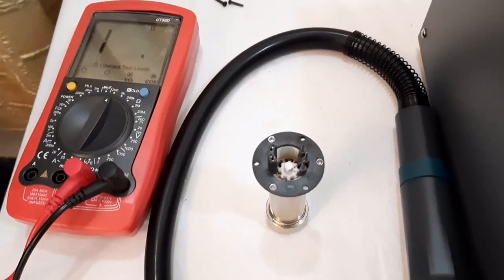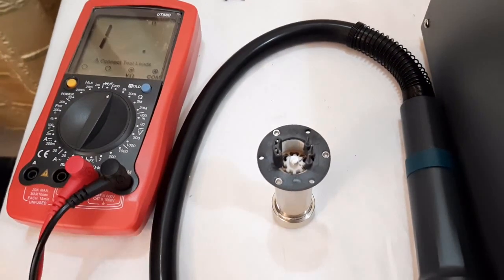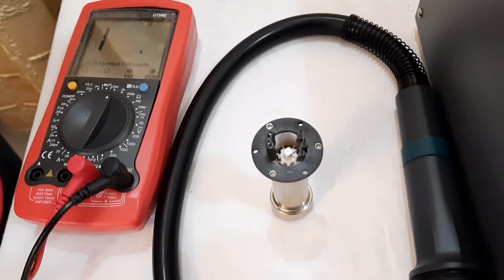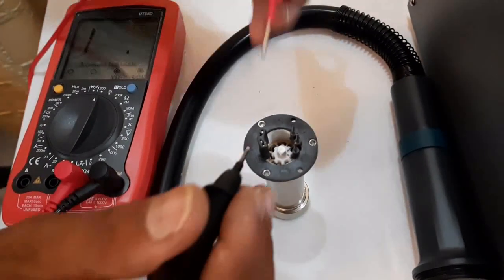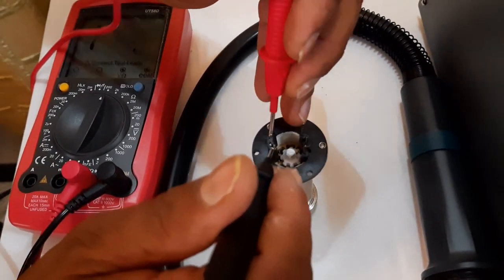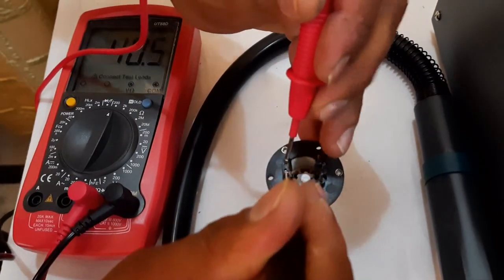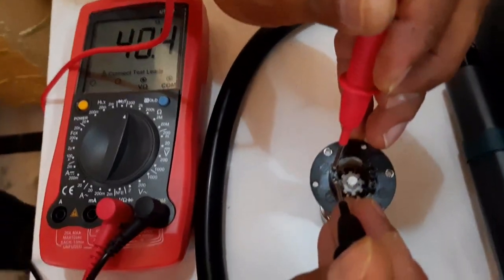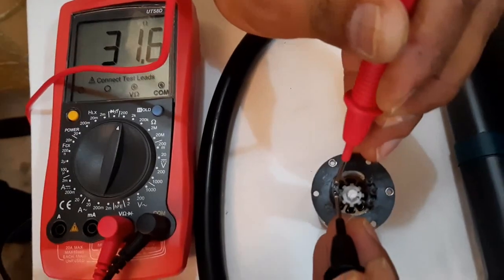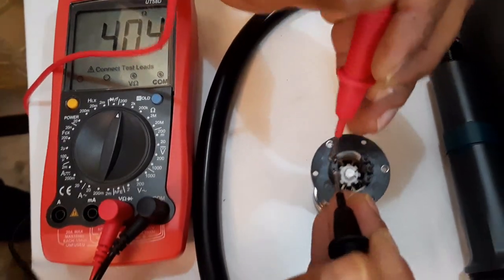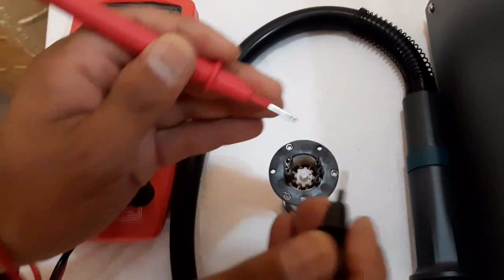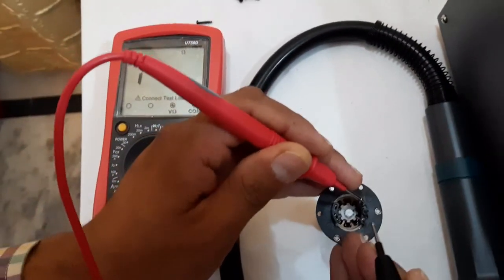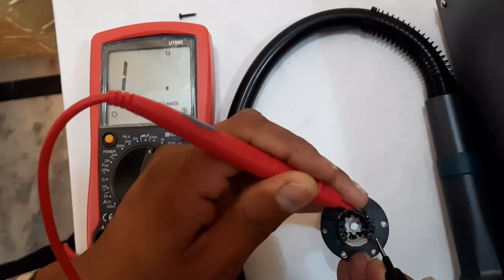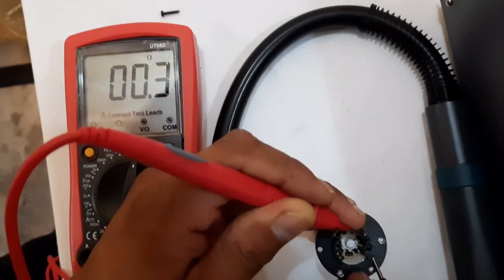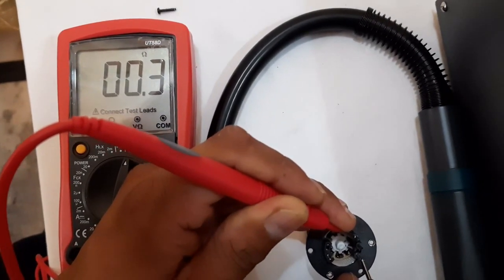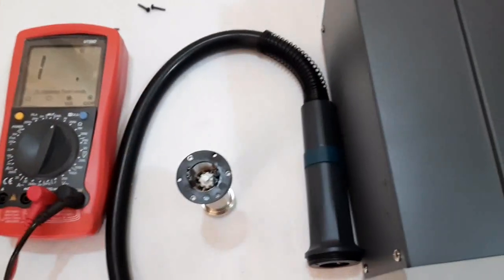Now we have taken a brand new heating element. We will verify first whether it is okay or not. We will measure the resistance of the sensor first. It is less than 50 ohm. It means the sensor is now okay. And similarly we will measure the resistance of the heating element as well. It should be less than 2 or 3 ohm. Yeah, it is less than 2 ohm. It means now the heating element and the sensor both are perfect.